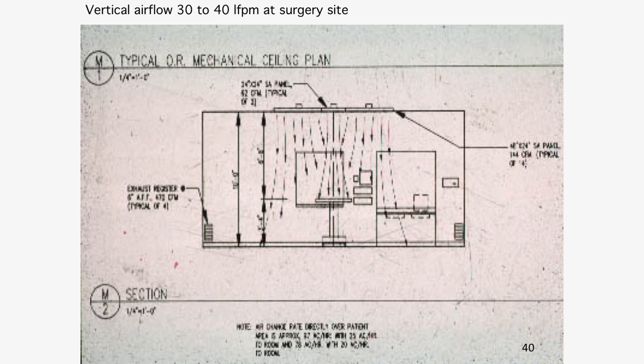Slide 40 tells you the ideal: blow the air straight down, don't impede it with false panels and overhead utilities that articulate in. They should be off to the side and articulate in, so the air can blow straight down with an air velocity of around 30 feet per minute over the surgical site, which allows the air over the surgical site to be purged constantly. As long as nobody's working up above, that's a nice way of creating a laminar flow-like regime.